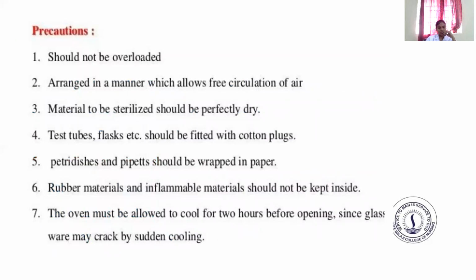And then precautions. It should not be overloaded and should be arranged in a manner which allows free circulation of air. And third one, material to be sterilized should be perfectly dry, and test tubes, flasks, etc. should be fitted with cotton plugs, and petri dishes and pipettes should be wrapped in paper. Rubber materials and inflammable materials should not be kept inside. The oven must be allowed to cool for 2 hours before opening, since glassware may crack by sudden cooling.